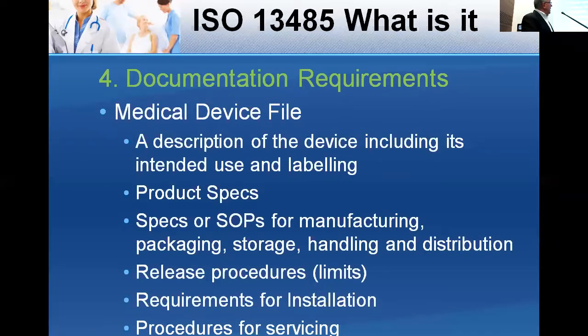There's a requirement now for release procedures and limits of what you're going to accept on your device. Those need to be in your medical device file. Records of installation and servicing are also part of your medical device file.